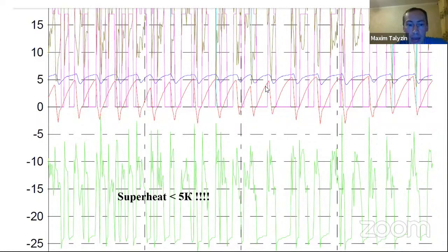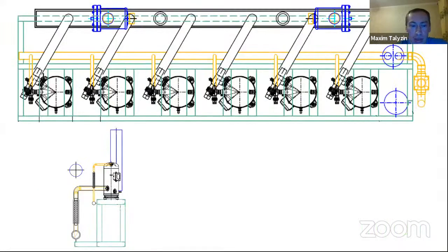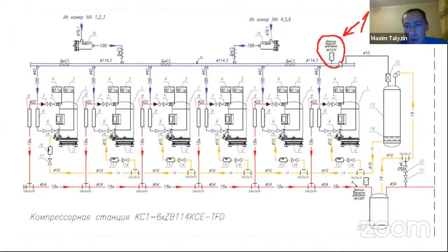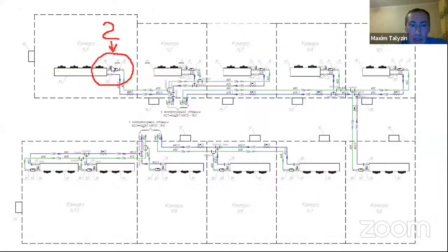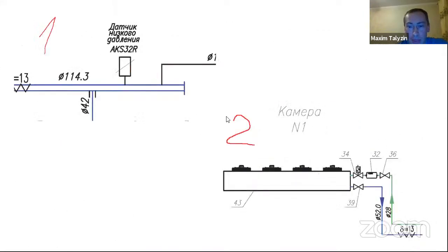I got this, and from the first look it looks okay. It's a suction line and discharge line. After that, I asked him to send me a PID, and I noticed that the pressure sensor was installed directly on a suction header. Okay, next step, I asked to send the PID of the cold room. I got it, and I noticed that an electronic expansion valve was installed. These 2 points that I noticed mean that one pressure sensor is used both for capacity control and for superheat control.